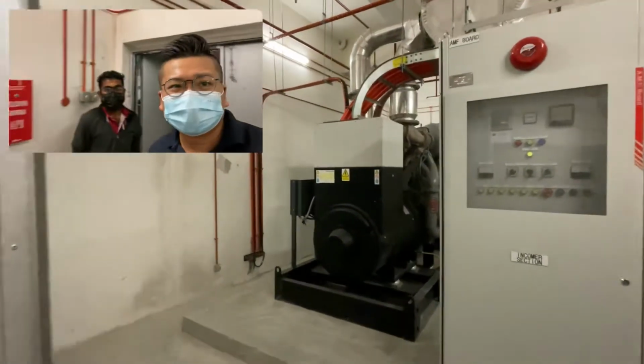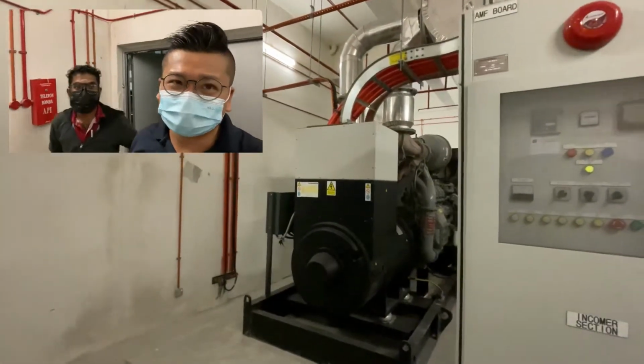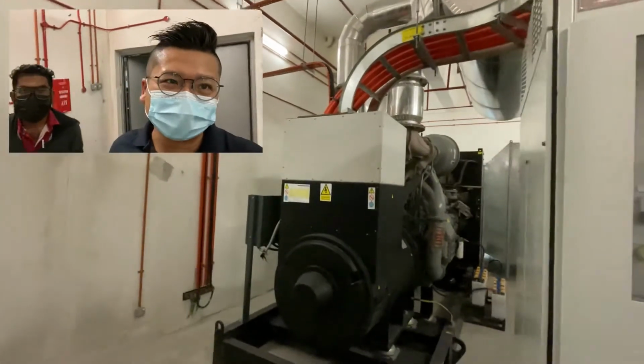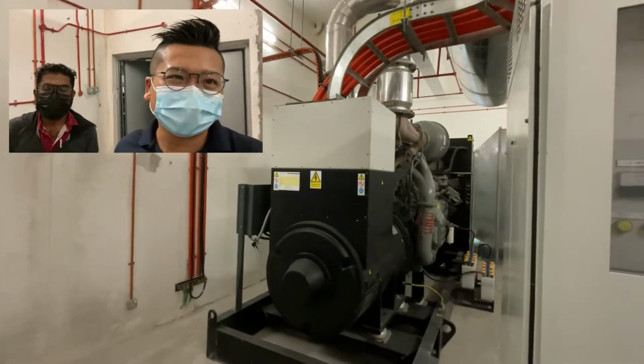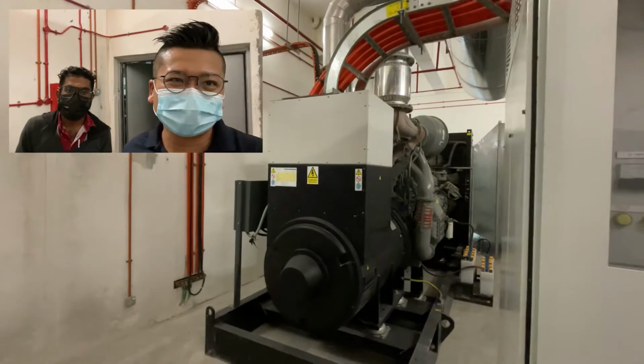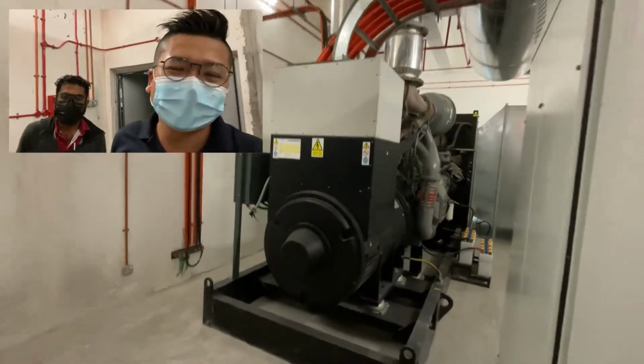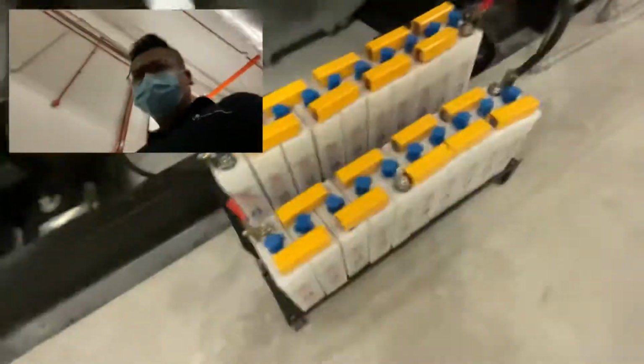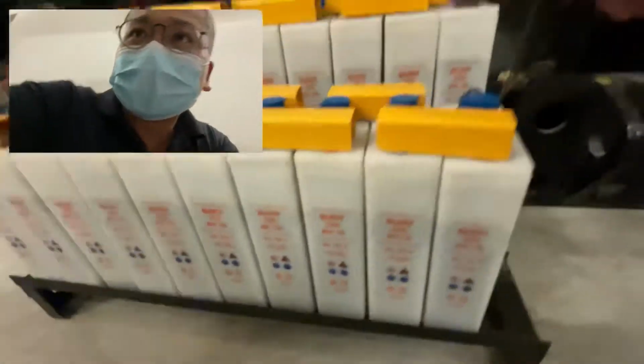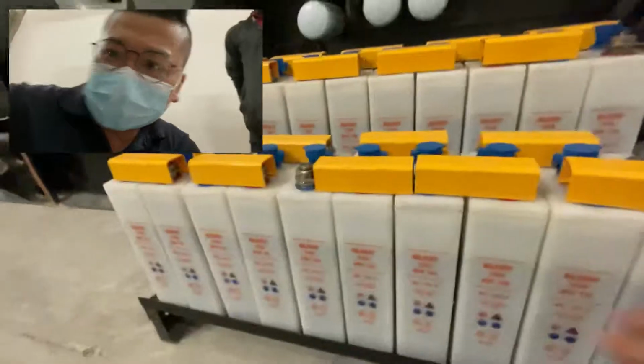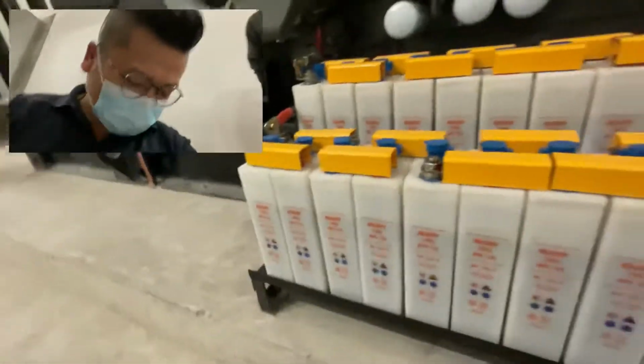Okay, this is the genset room. Now we're going to routine test the genset, but this genset is currently having some problem, not able to run, so we're going to have a general checking. Okay, first of all, we're going to check the battery. Make sure the termination is tightened. Battery water okay.